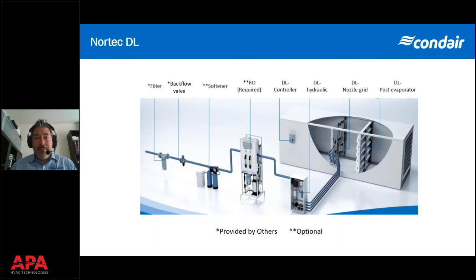I want to just say one thing here about evaporative humidification. If you have a building that's using an economizer and you can do enthalpy control, evaporative humidification is the only technology out there that you can actually save energy with throughout the year, meaning the energy you have to put into the water to humidify is more than offset by the extended economizer window. Typically, customers are seeing between 20 and 40 extra days a year of being able to run economizer with enthalpy control. And that's why we can humidify a whole building for less energy cost. I know that's important, especially in Boston and that area, but it becomes more and more important. So we can actually accomplish both. We can give your owner the humidity that they want if they're using an economizer and save them energy at the same time. Next slide, Graham.